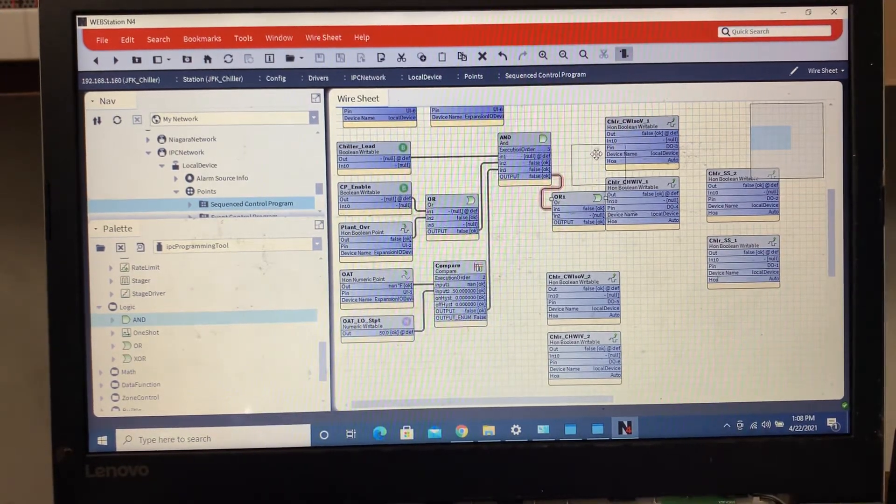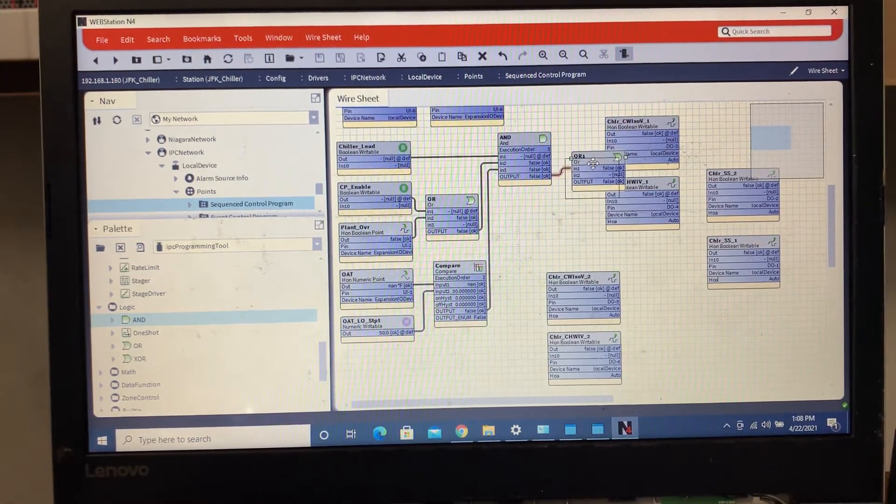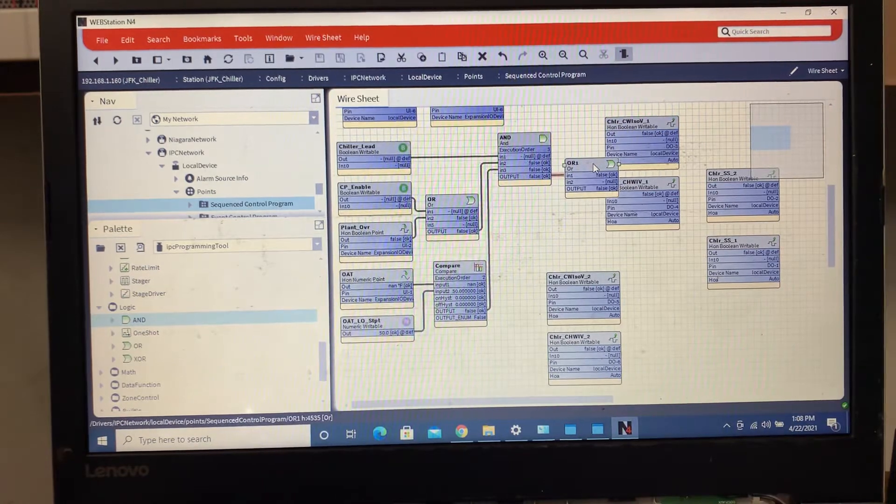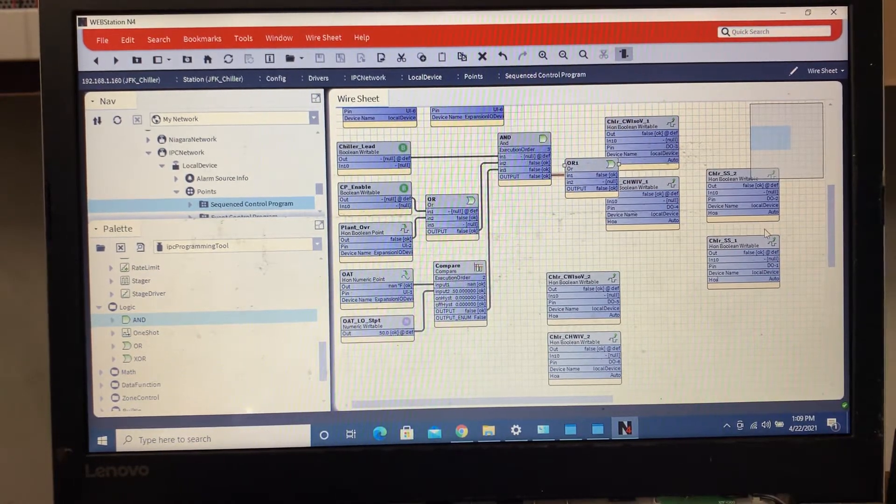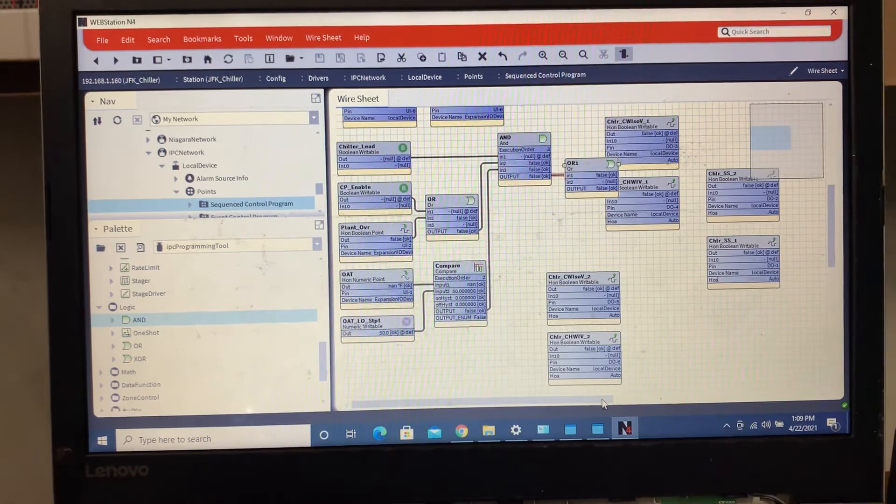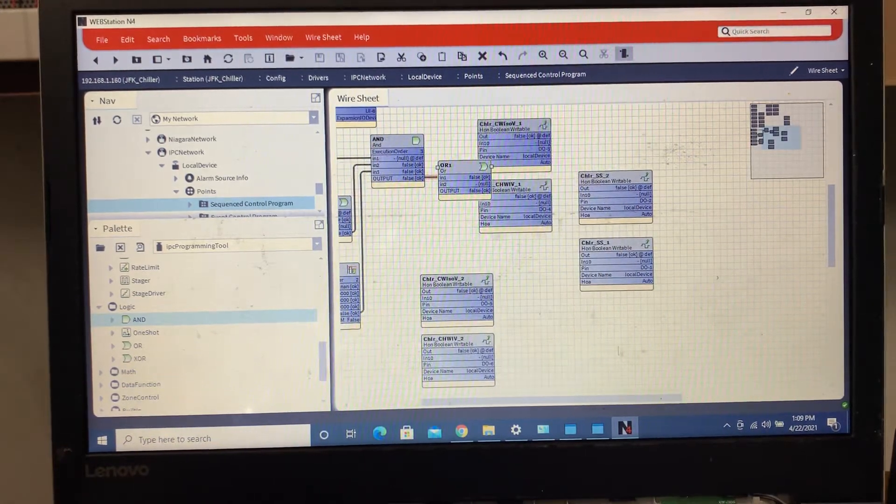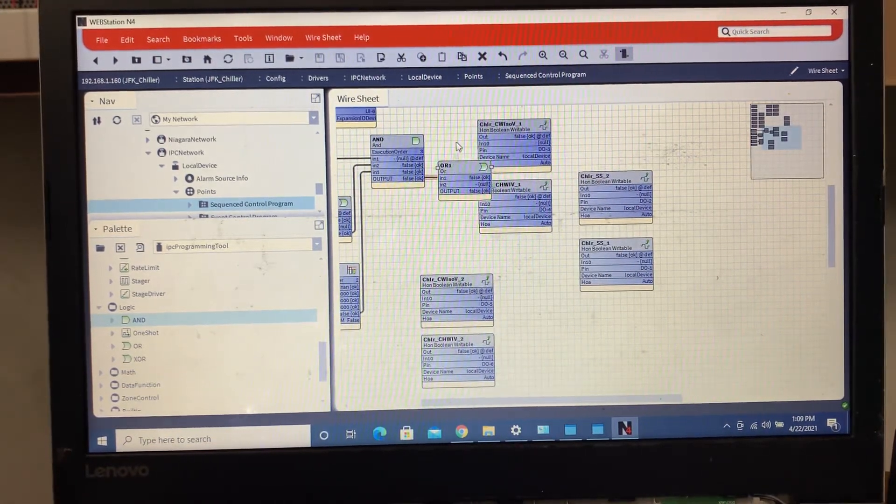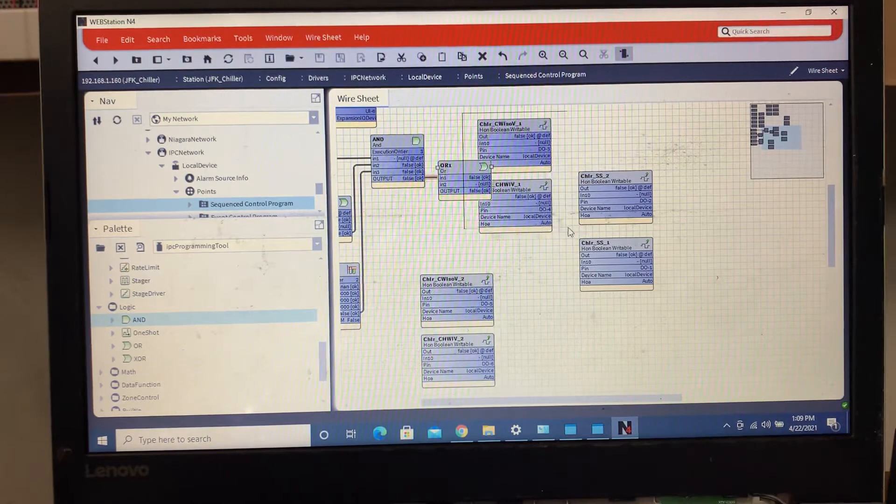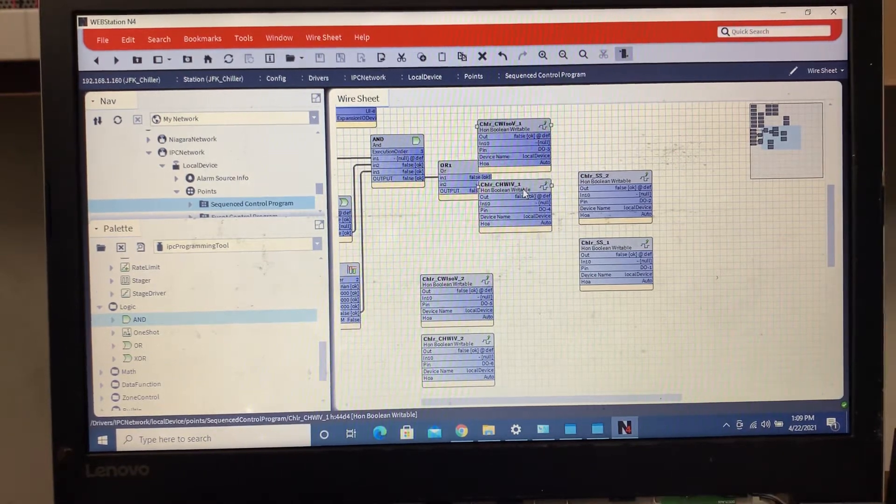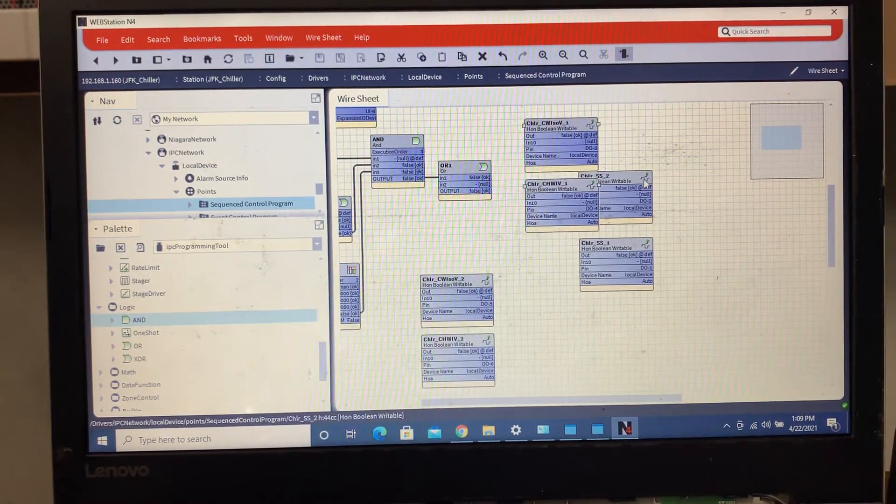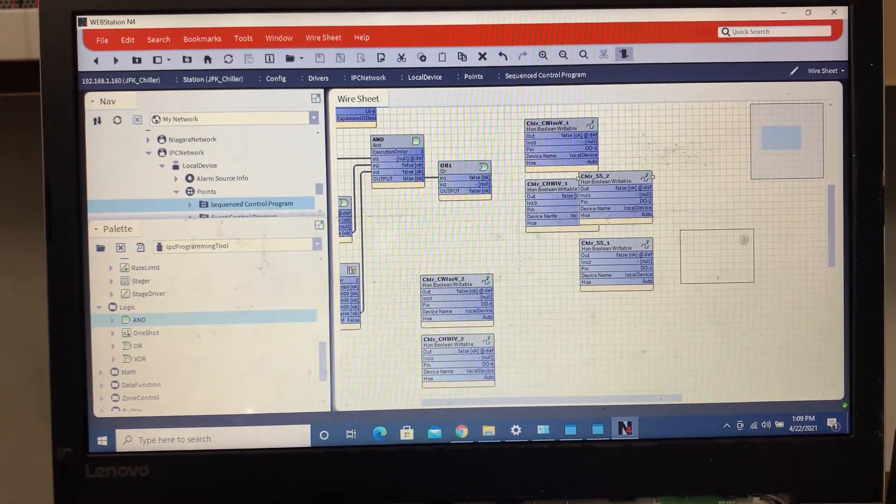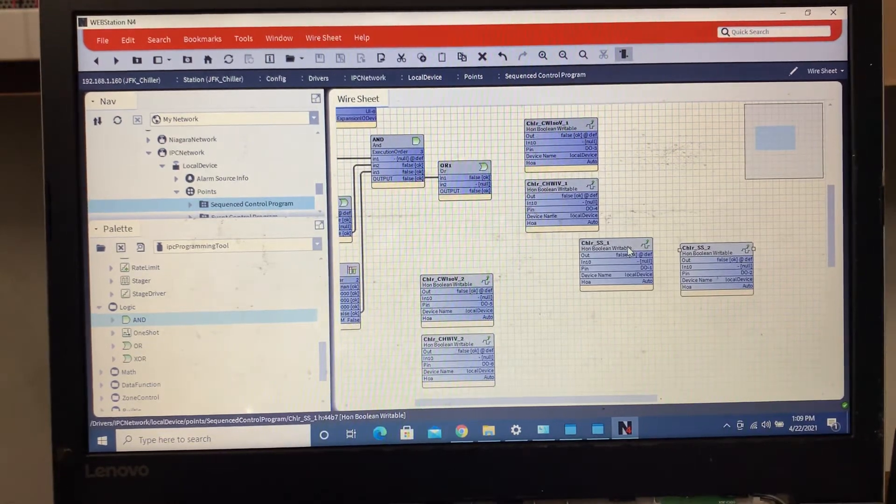Basically what we're gonna do is we're gonna create another block based on cooling setpoint for our chiller enable setpoints for the lead lag, where if the chill water starts getting above a certain temperature for a certain amount of time, we'll go ahead and it'll enable the lag chiller.